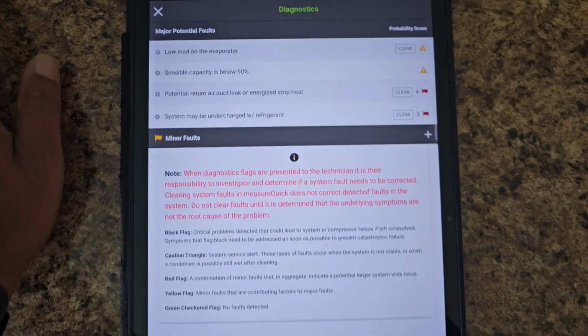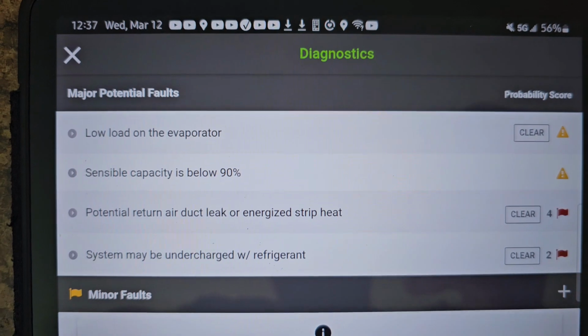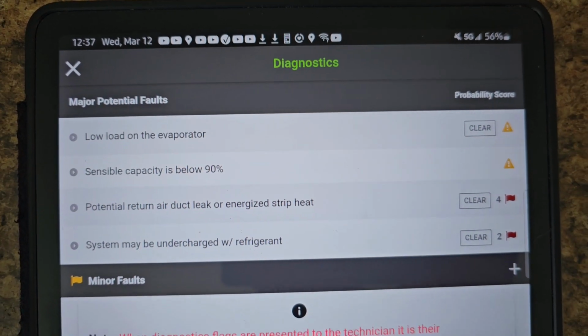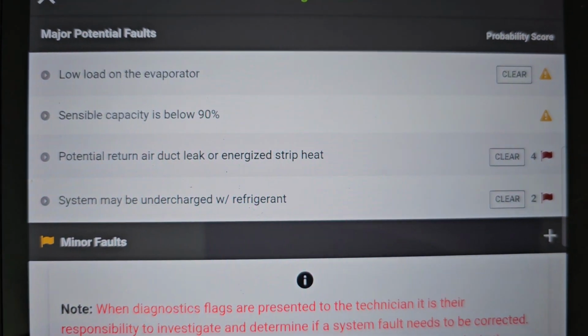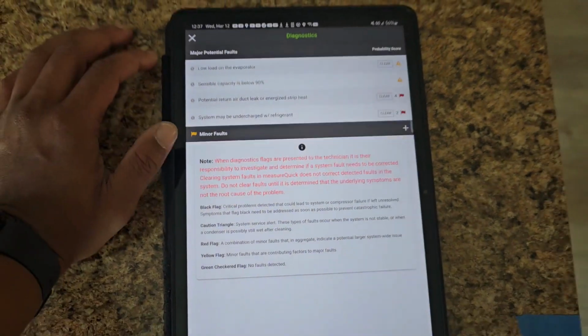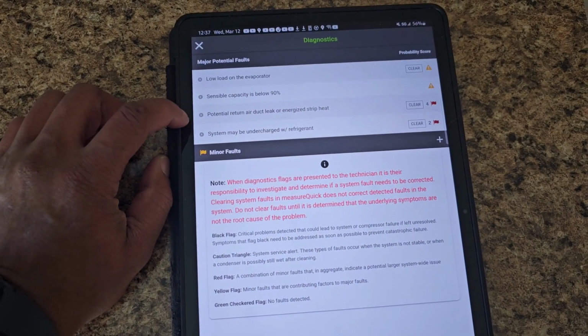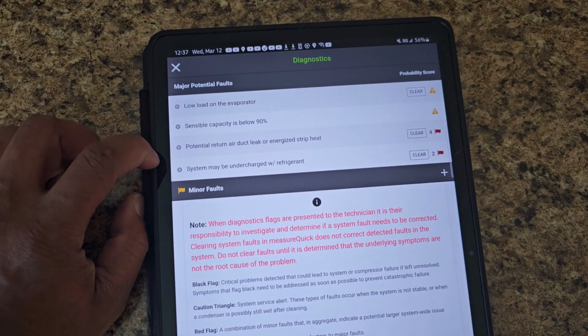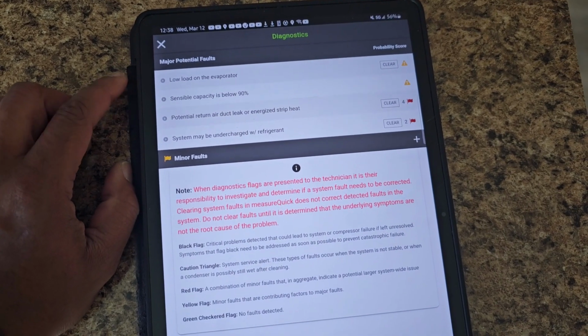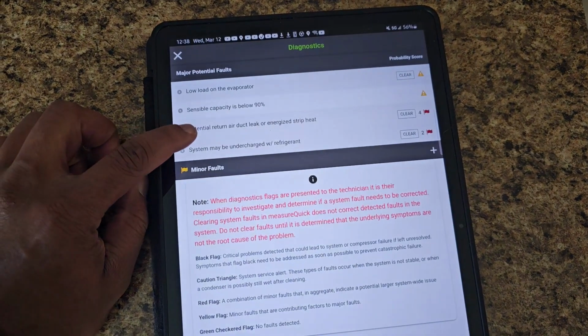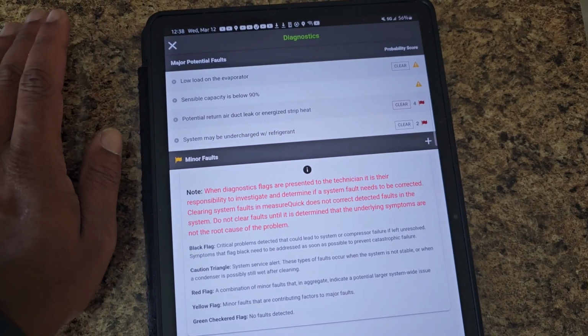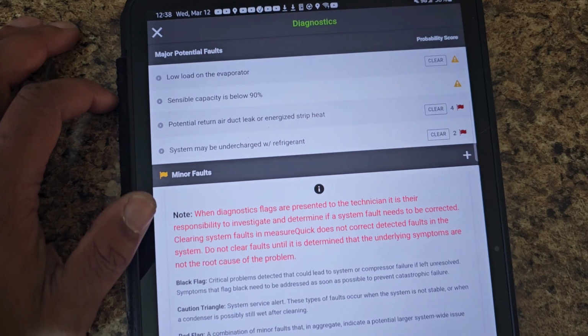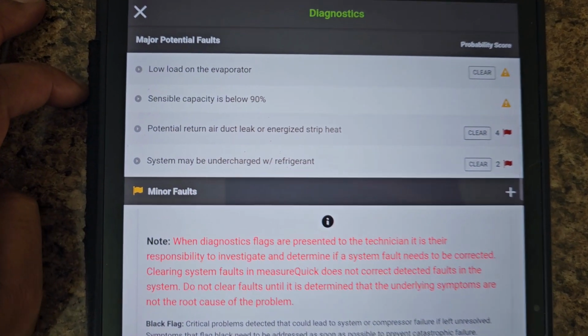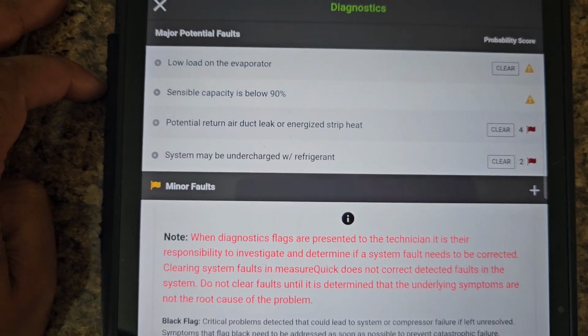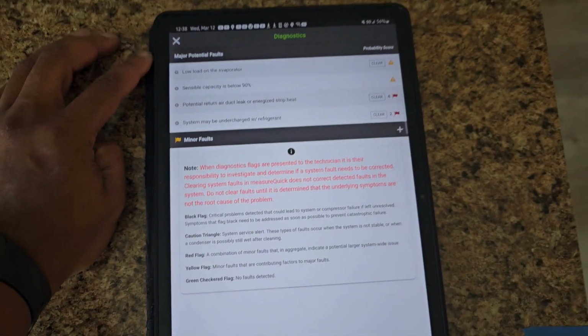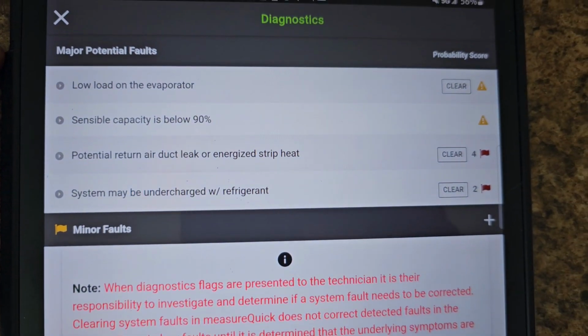But let's take a look at the faults. So yeah, low load on the evaporator. Sensible capacity is below 90%. Potential return air duct leak or energized heat strip. Now I will admit, I did just switch the thermostat straight from heat to cool, so I didn't let the heat exchanger take any time to cool off with the fan by itself. I just started the system up because I've been here for so long and I'm ready to go. But it says it might be undercharged with refrigerant, and I would prefer to wait for a hotter day to be okay with that as the fault code.